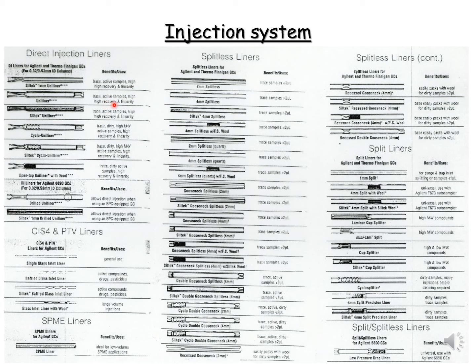You have the different properties of the liner with, for example, the diameter, and whether there are modifications, derivatization, or additions in the liner, etc. Then the nature of the injector: this is a liner for direct injection, here a liner for splitless injection, in that case a splitless 2 and a split liner. So you can choose your liner depending on the nature of the injector.